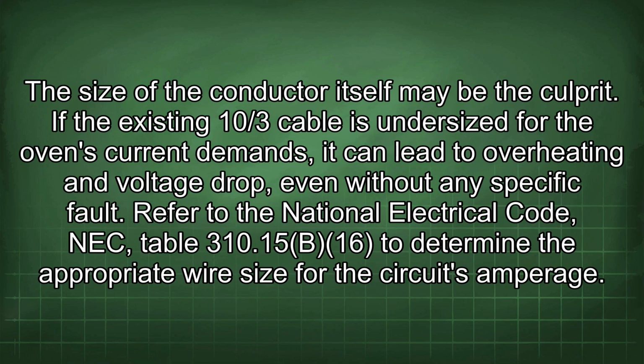The size of the conductor itself may be the culprit. If the existing 10/3 cable is undersized for the oven's current demands, it can lead to overheating and voltage drop, even without any specific fault. Refer to the National Electrical Code (NEC) Table 310.15(B)(16) to determine the appropriate wire size for the circuit's amperage.